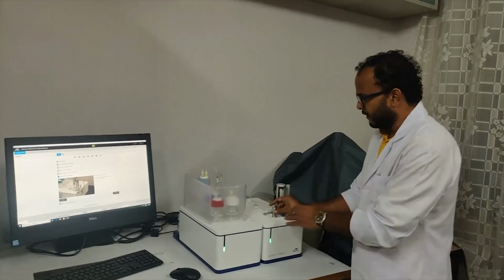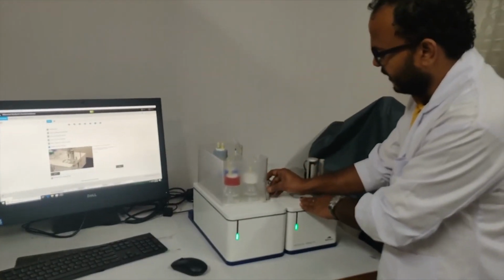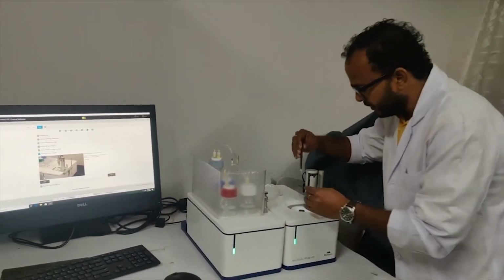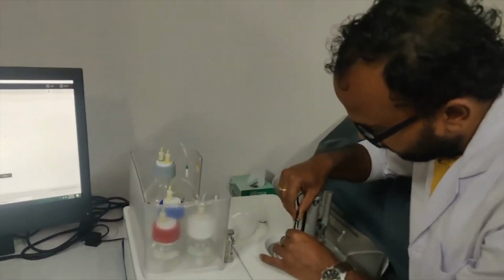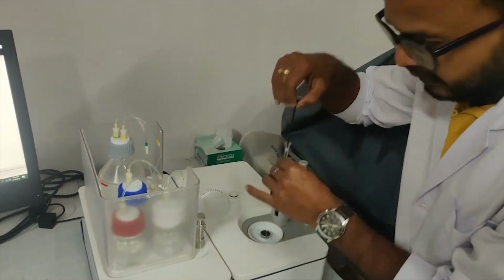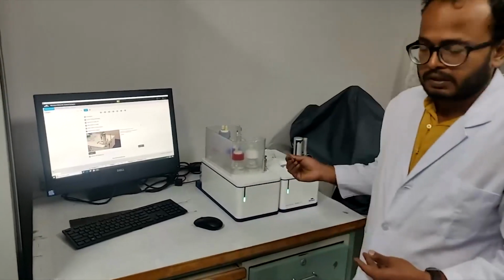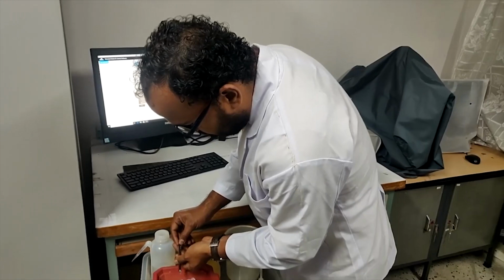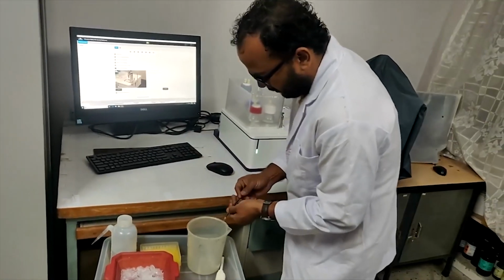After cleaning, we need to remove this cell cleaning tool from the cell, and after that, using this loading syringe, we need to first take out whatever is left inside the cell after cleaning. So we will discard these things. Now we have removed everything from the cell. Now we will wash this syringe first with water, and then with the buffer, 3 times.